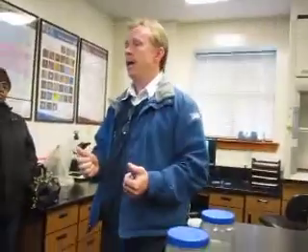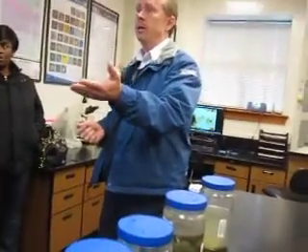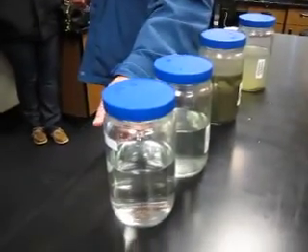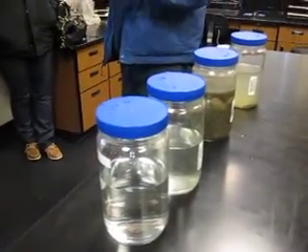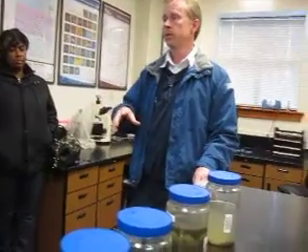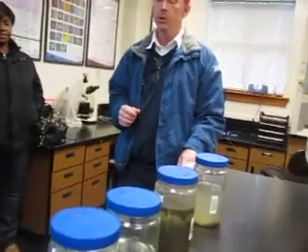So right now, instead of treating, let's say our flow right now, Mike, would probably be 17 or 18, it might be 24, 26 coming in. Right now it's 27. All right, so we're close to 28. So you can see how much 1 inch of rainfall has increased our flow. Now, on a regular day, it would be almost hard to tell the difference between the two, but when you get that much flow, it has a tendency to stir things up a little bit, especially in the secondary clarifiers, especially when you've got one of your clarifiers out of service for maintenance, which we do now. But it's still good. It meets all the permit limits, and we're in good shape there.